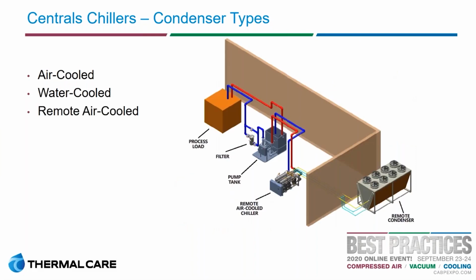And then finally, we have a remote air-cooled chiller. Basically, if you can imagine that first setup with the air-cooled chiller, the packaged unit that was sitting outside, what we've actually done is split that into two pieces. We have the chiller with the refrigeration circuit inside of the facility. And then on the outside, we have what we would call the condenser, the remote condenser. That houses those fans, where it uses that air to force that heat out of the system and into the atmosphere. So the only thing connecting these two items is actual refrigeration copper piping. What this allows you to do is have the chiller inside, so that water is never being pumped outside. So you're never exposing the water to those ambient conditions, and you could potentially avoid a glycol solution if you wanted. Then we're still able to reject that heat outside of the building. So this is a very elegant solution for taking the benefits of an air-cooled system, but also avoiding some of the downfalls of that outdoor system.